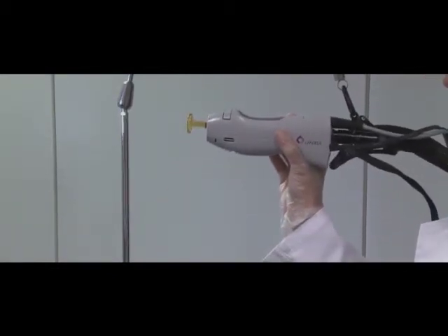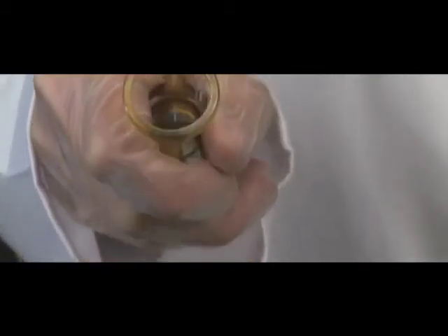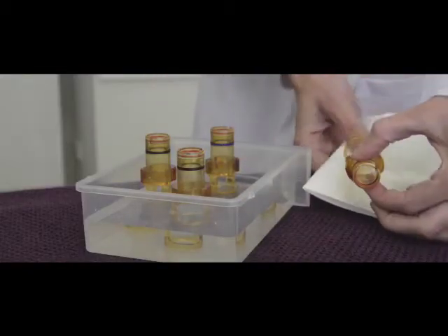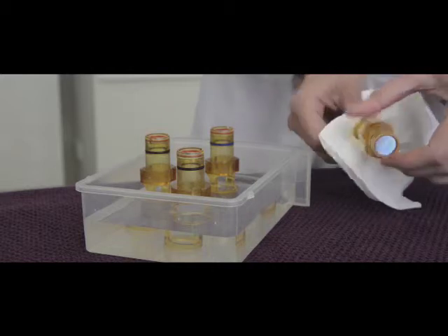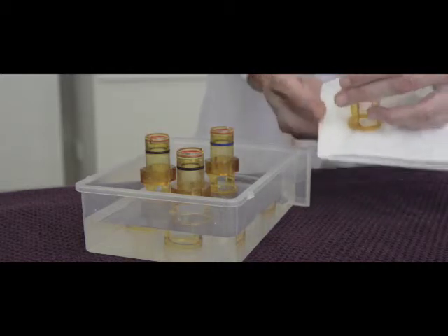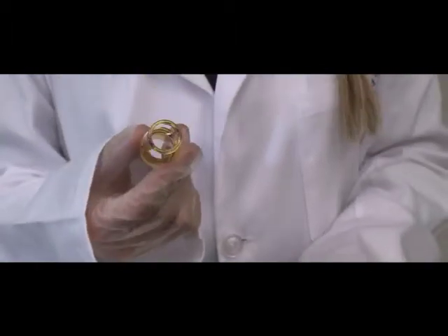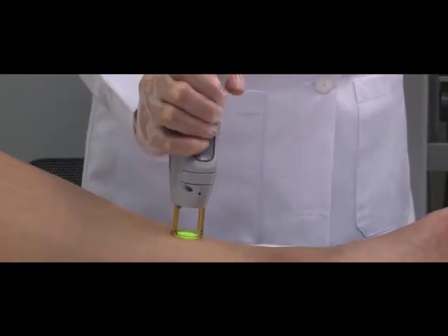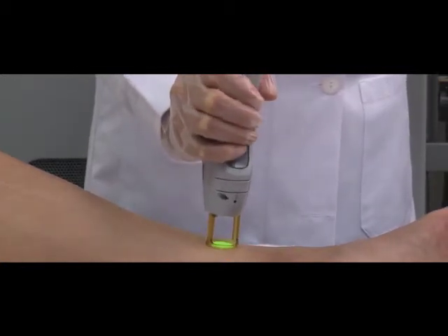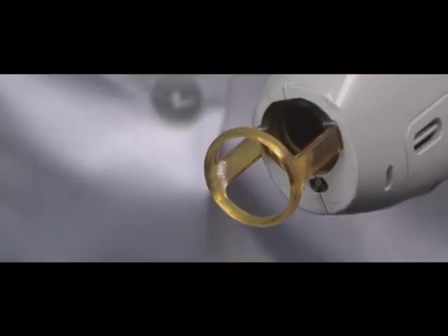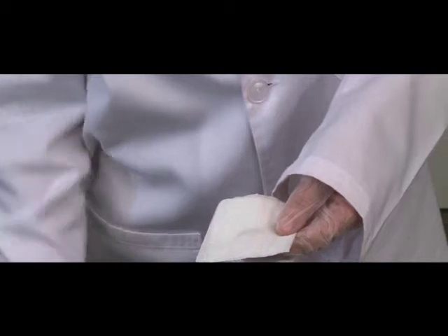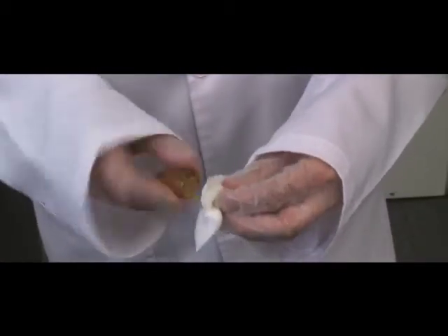Make sure your distance gauge is clean and has no black stain on it. If it is developing black stains, you may clean the end with a diluted bleach solution. Change your distance gauge every 200 to 300 pulses. A clean window and fresh gauge can be quickly and easily attached. Also during the treatment, keep the distance gauge free of any frost from the cryogen by quickly wiping every 30 to 40 pulses. And, of course, clean with isopropyl alcohol or medical wipes between patients.